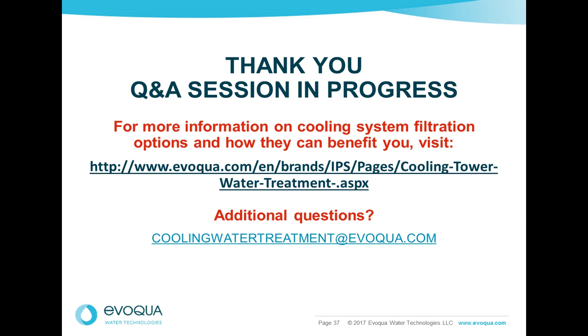I agree, Bob, and the only thing I would say, though, is don't look at it from a day-to-day view. Trend it over time, because there may be a few peaks and valleys depending on what's going on in the system. So watching the trend of turbidity is another good way. Good point. Yeah, you're going to see highs and lows. Spring is going to be a dirty point, and winter will be a low point.